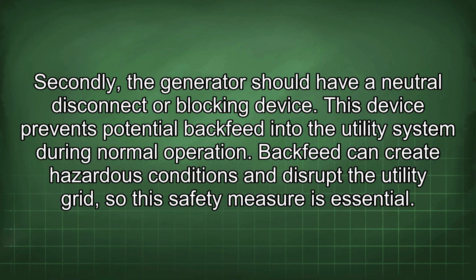Secondly, the generator should have a neutral disconnect or blocking device. This device prevents potential backfeed into the utility system during normal operation. Backfeeds can create hazardous conditions and disrupt the utility grid, so the safety measure is essential.